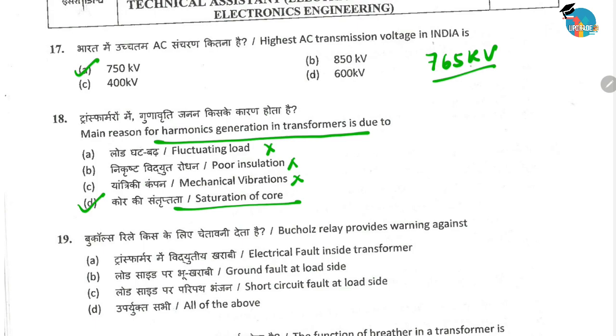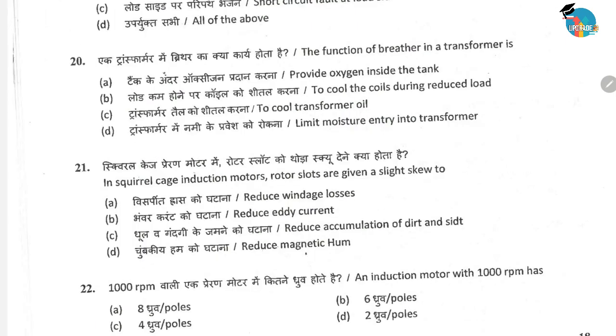Next question is Buchholz relay provides warning against. Options are A, electrical fault inside the transformer. B option is ground fault at load side. C is short circuit fault at load side, or D is all of the above. As we all know, Buchholz relay provides protection against the internal fault in a transformer. So the correct option is option A, that is Buchholz relay provides a warning against the electrical fault which happens inside a transformer.